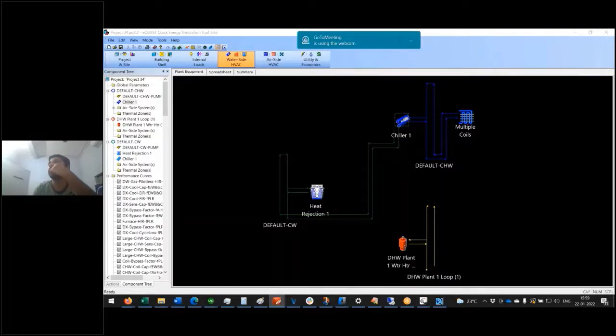Thermal comfort is a function of your wind velocity and also the relative humidity. It's not just temperature. So you need something which measures the relative humidity of the incoming outdoor air, and then the speed at which the mechanical ventilation is throwing in the air. That velocity has to be varied as per the temperature and relative humidity. So yes, it can be done if you have that good amount of control, but again your fan size is going to increase definitely.